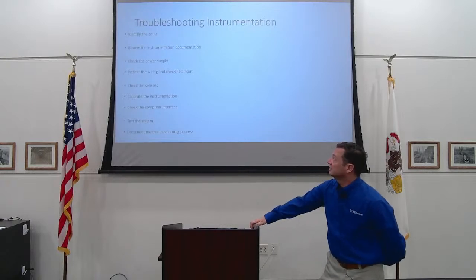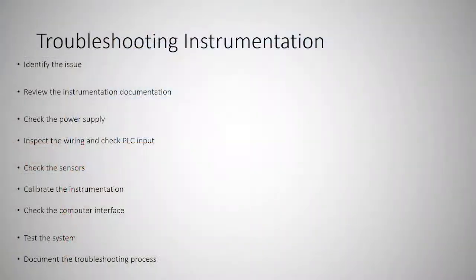Troubleshooting instrumentation. Obviously, the first step is to identify the issue, and in my opinion, it's go to SCADA, right? You go to your SCADA system, you go to your HMI. Is it reading incorrectly? And then go verify the condition in the field. Get whatever documentation you can on the device before you go out and look at it, unless it's a device that you know very intimately, something you already have familiarity with.